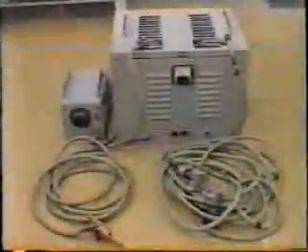Clearly, at these low values of secondary current, great care must be taken in order to obtain accurate readings. Some companies use a larger test set in order to provide a higher value of primary test current, and so check operation of the relay itself in addition to verifying CT connections. Test sets may be rated up to, say, 10 kVA, with the capability of providing up to 1,000 amps at 10 volts.